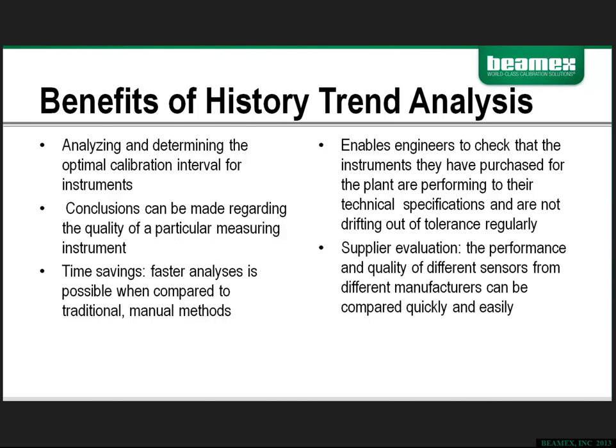There's a time savings involved, and I referenced that a little bit. Doing this manually, and I'm not sure which of you may have done this before, is extremely time consuming. It requires a lot of documentation, and the analysis that you actually have to do in terms of comparing data can wind up taking you much longer, which would somewhat consume the time savings that you would have by using automated software such as the CMX calibration software with the history trend module.